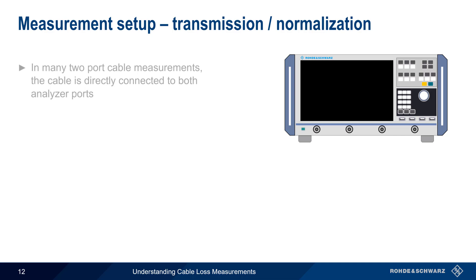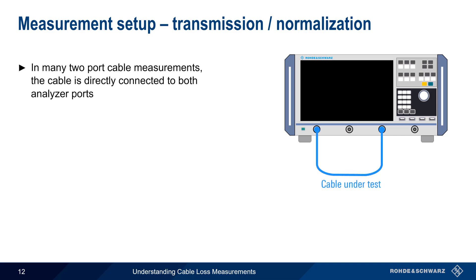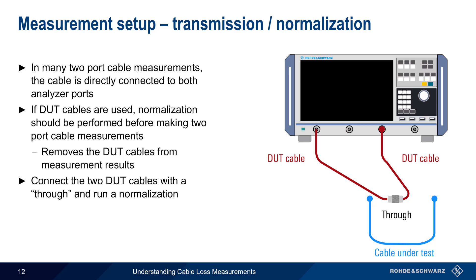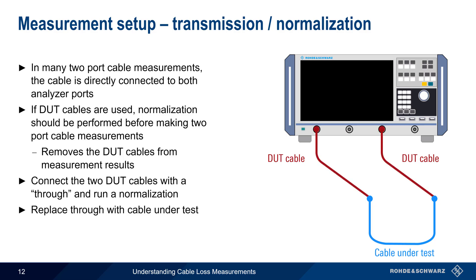In most two-port cable measurements, the cable under test is simply directly connected to both analyzer ports. If however DUT cables are used to connect the cable under test to the analyzer, then a normalization should be performed to remove the influence of the DUT cables from the measurement. To perform a normalization, the two DUT cables are connected using a THRU. After normalization is complete, the THRU can be replaced with the cable under test and measurements can be performed.